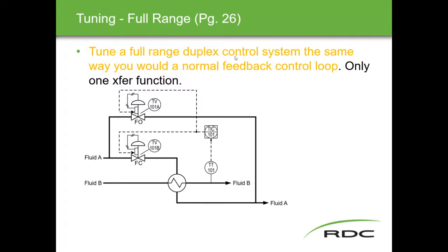To tune the full range duplex control system, you tune it the same way you would tune a normal feedback loop. There is only one controller, so there is really only one transfer function. Both loops are flow loops, so they are both fast — tune one, then tune the other; nothing fancy required.